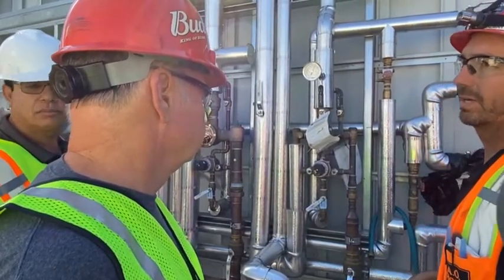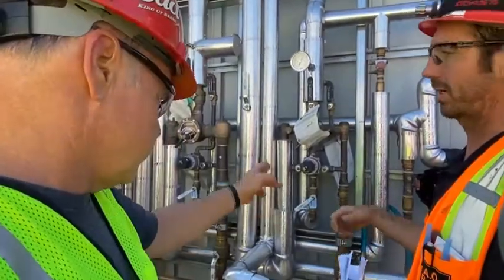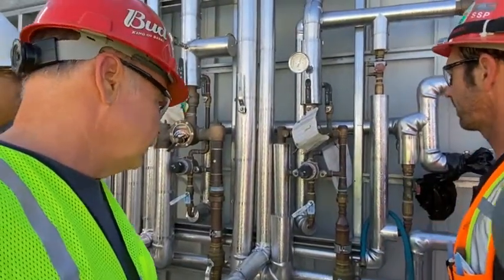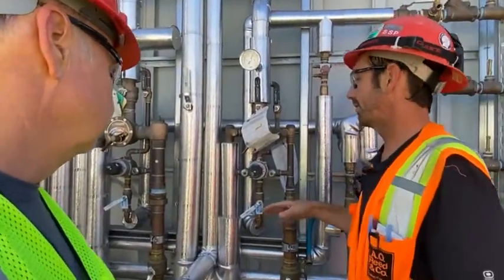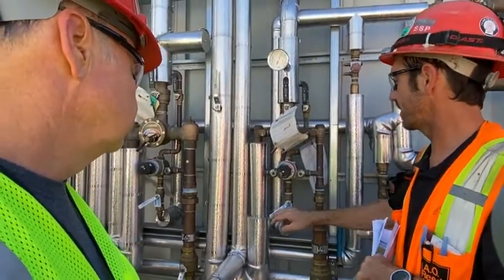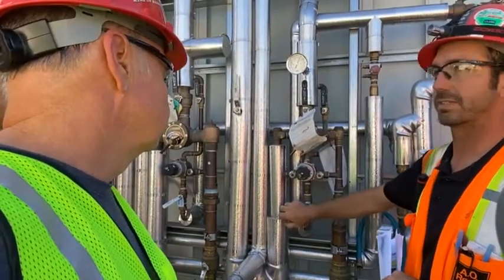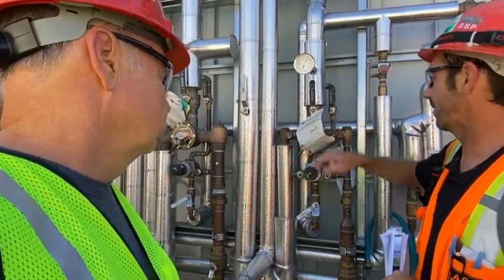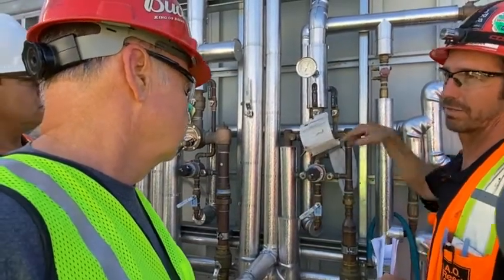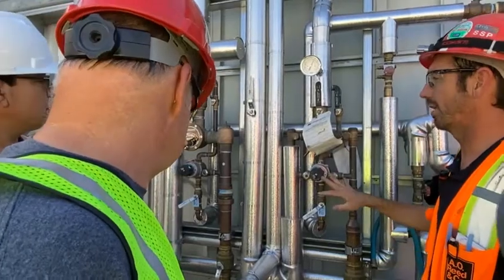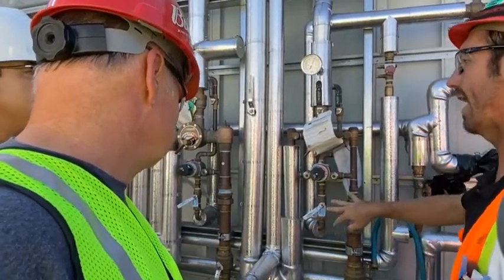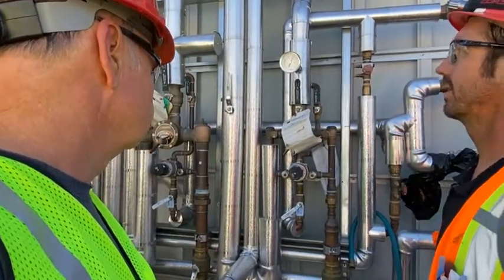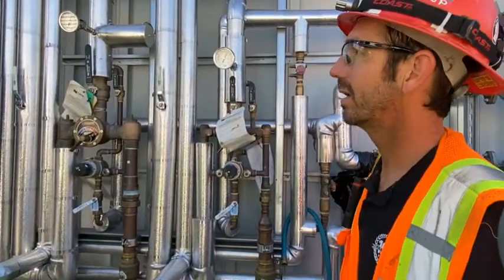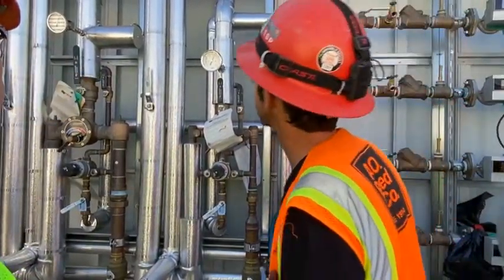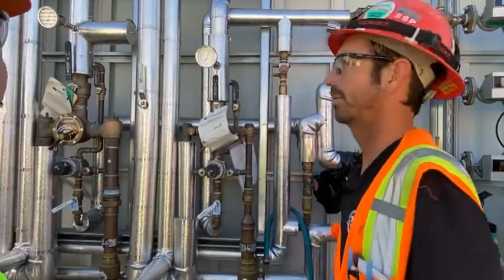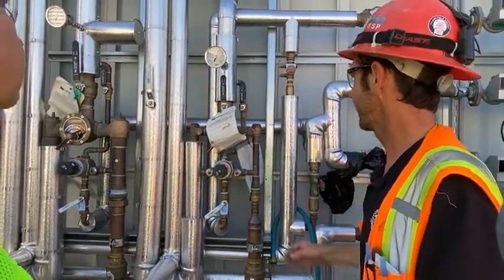But with no flow, make sure when they turn on the sink and it's 120, it's running through this line right here. If something weird happened in the system and the sink temperature goes up, you can open this valve more. If the temperature is down, then you want to close this more and let more water go through the 147. But they have been balanced right now where they're at, both systems. What do we got? 119. 118.9 or something. Okay.